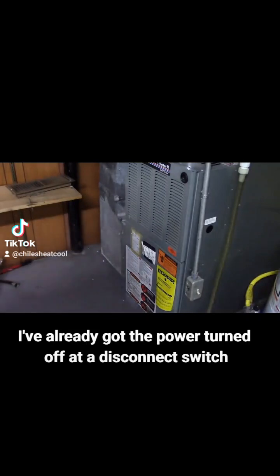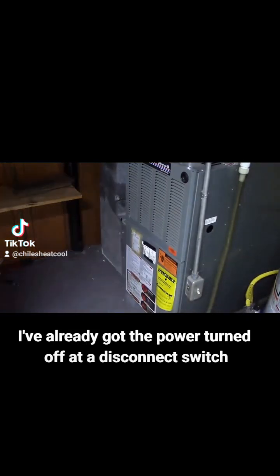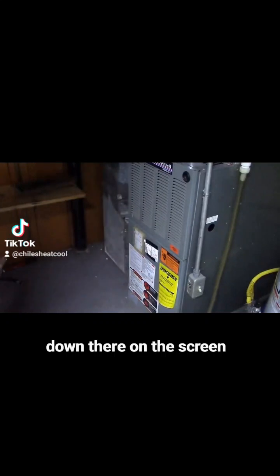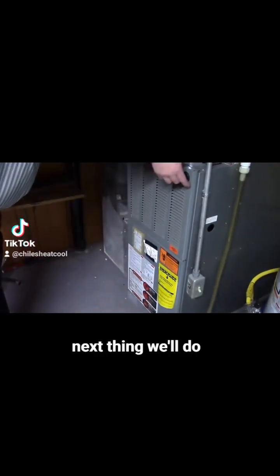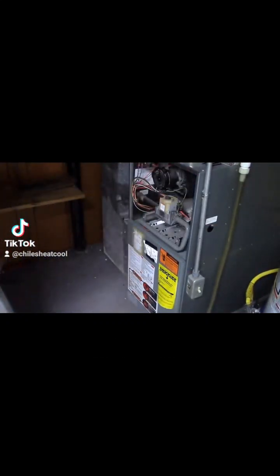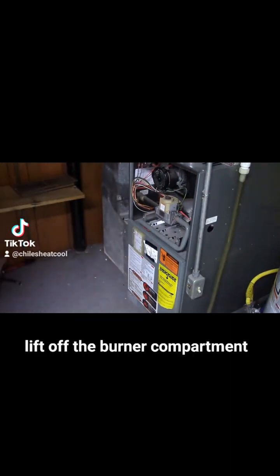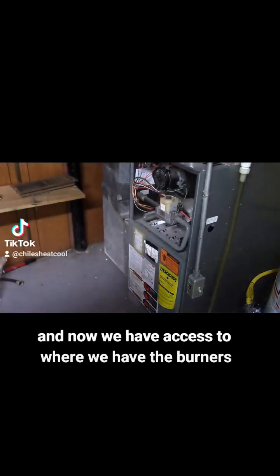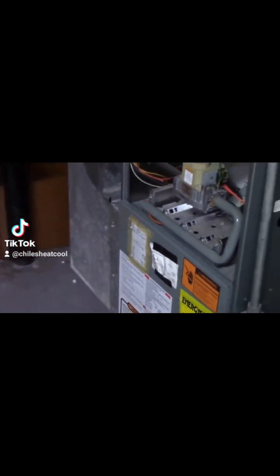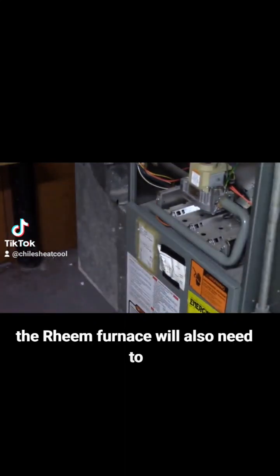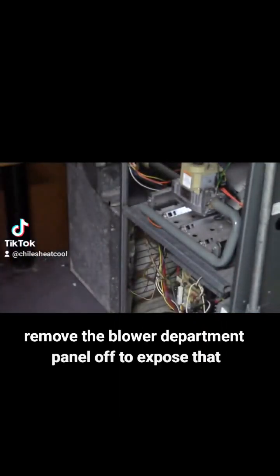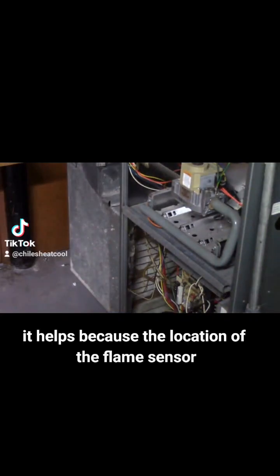I've already got the power turned off at our disconnect switch down there on the screen. Next thing we'll do, lift off the burner compartment panel, and now we have access to where we have the burners. The Rheem furnaces, you'll also need to remove the blower compartment panel off to expose that. It helps because of the location of the flame sensor.